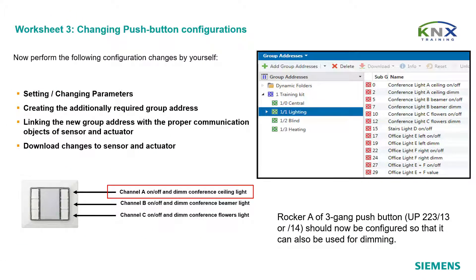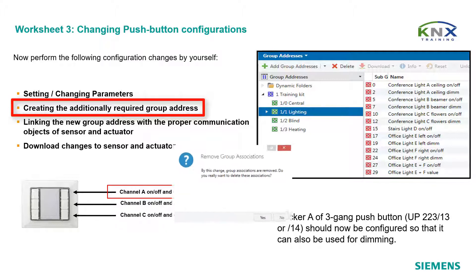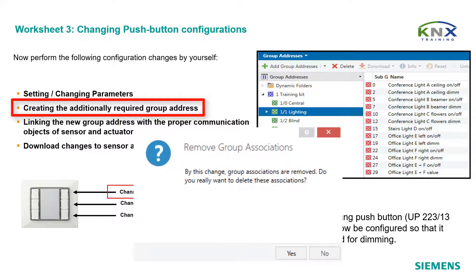Changing push button configurations. The first change to be applied is the function of conference ceiling light A on the switching dimming actuator. Instead of purely switching, now also dimming should be enabled. Try to do the required steps on your own. Start with the parameters of the push button, then create the new group address. When you change the rocker configuration of rocker A, ETS will prompt you to accept that group address links will be removed — you must accept it in order to proceed.